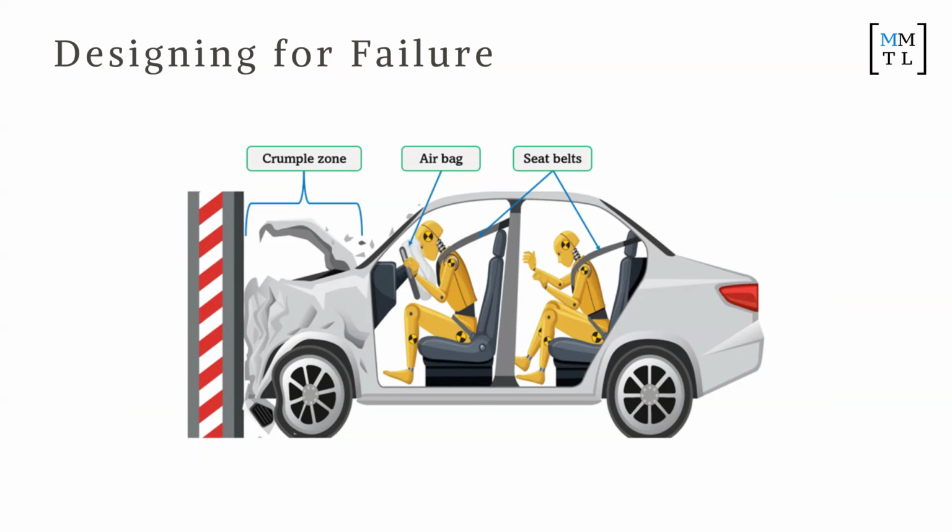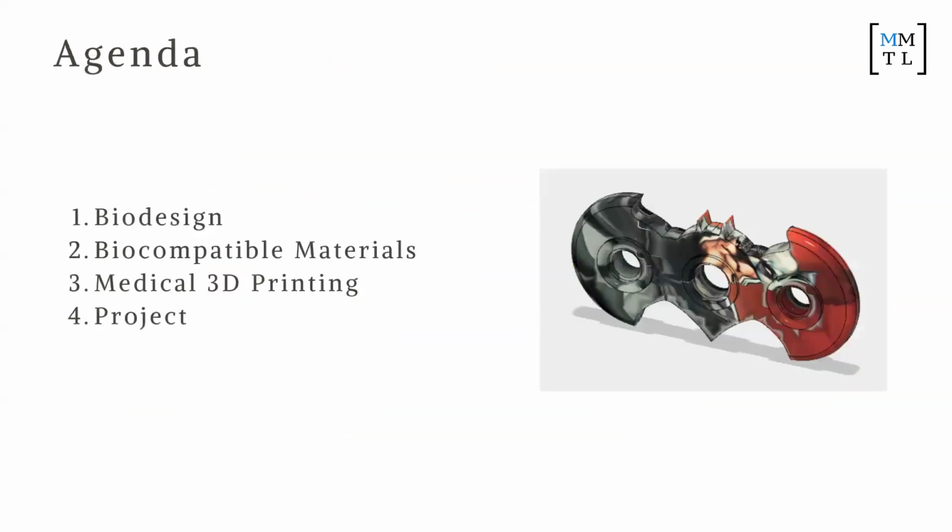So when we're working, for example, on our medical device, we ask: if there is a voltage spike of 50 volts, what is actually going to happen to the device? Is the patient going to get killed because there's a shock? Or are there internal mechanisms that kick into place and protect the patient? Okay? So again, just thinking about designing for failure.